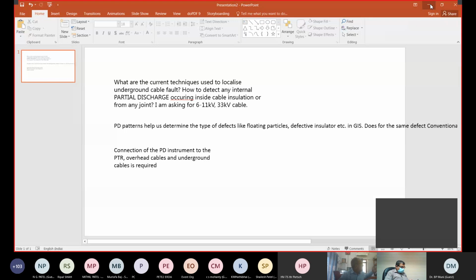The other thing is if you have a frequency resonant test system and operate at, say, 30 Hertz, while the power frequency - for example in Europe, 50 Hertz - you can definitely distinguish external noise from real PD very easily, because the phase correlation and frequency repetition rate are correlated to the external frequency. That's one of the big disadvantages if you only have the power supply amplitude at 50 Hertz on site. That's my answer.